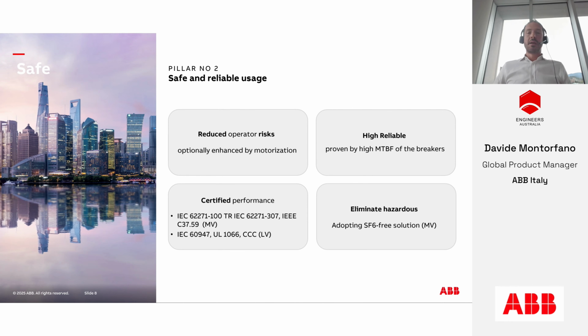Also, being aligned to the latest standard definitely improves a lot the reduction of the risk compared to the past. An option that is available for some specific designs of our retrofit is also applying operation from remote. Typically, rack in, rack out of the breaker from remote, and opening and closing the breaker from remote. This reduces drastically or eliminates the risk for the operator because they avoid human error in doing the operation. And of course, if something happens, the operator will not be in front of the panel. This is really a very high improvement for the safety of the operator in the plant.